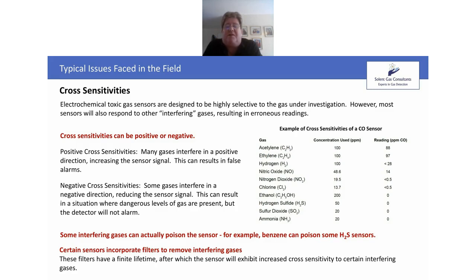Negative cross sensitivities can be worse, because you could potentially come to a situation where there's a dangerous level of toxic gas present, but because the signal is reduced, it may not alarm in dangerous situations, and obviously that would mean life may be at risk. There are certain things you can do to try and counteract this. Commonly, sensors would include filters, as I mentioned earlier, to chemically remove interfering gases. These filters tend not always to last the life of the sensor, and once a filter capacity is used up, then the sensor would start responding to interfering gases.